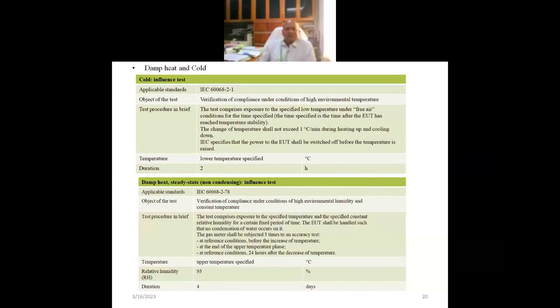The gas meter shall be subjected 3 times to an accuracy test at reference condition: before the increase of temperature, at the end of the upper temperature phase, and at the reference condition 24 hours after the decrease of temperature. Relative humidity would be 93% and duration 4 days.